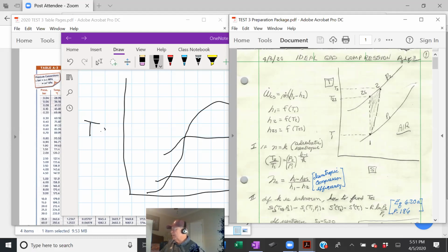We call it adiabatic isentropic reversible compression. That's our ideal. That's what we measure against. What we actually get is an increase in entropy, and this increase in entropy is due to irreversibilities, and most of these irreversibilities, 90 to 95% of them, are visible, or measurable, in the form of heat transfer from, in this case, our compressor.